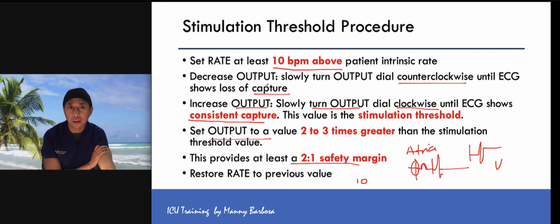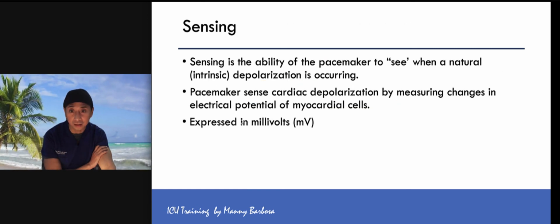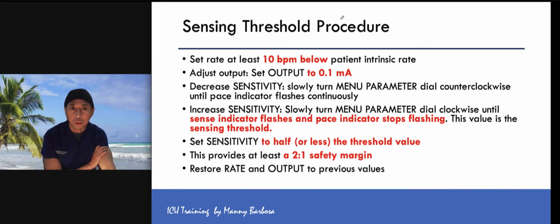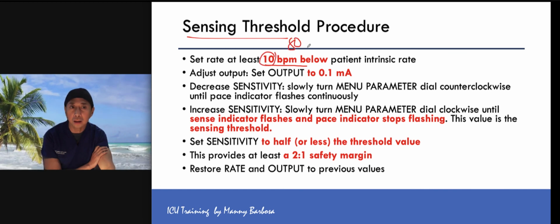Okay, so again, stimulation threshold, you're stimulating, so you need to double it once you get a consistent capture. Sensing, you're sensing, right? So what you do is, this is what the pacemaker is seeing, your own intrinsic heart rate. So how do you do the sensing threshold? So your machine rate should be below the patient's. So 10 below. If my heart rate is 80, give me 70 on the pacemaker.